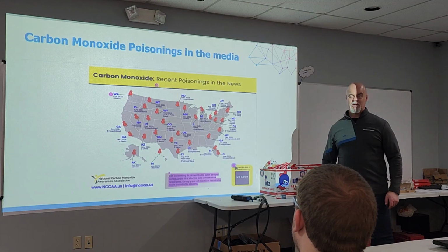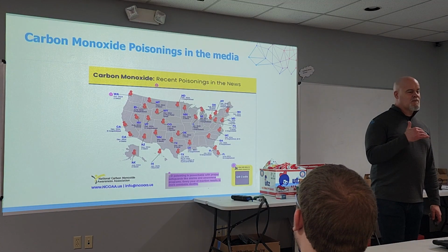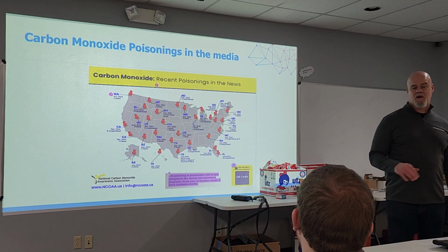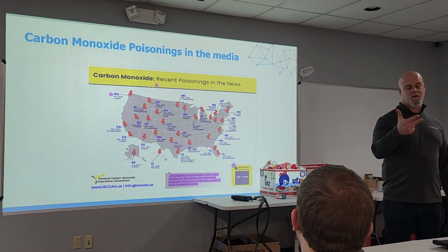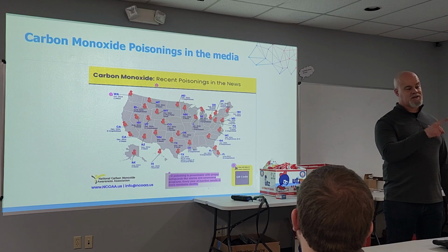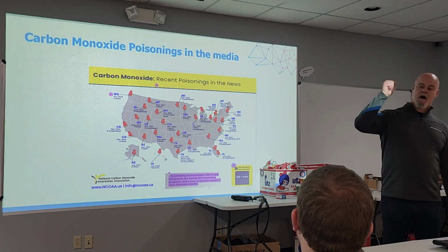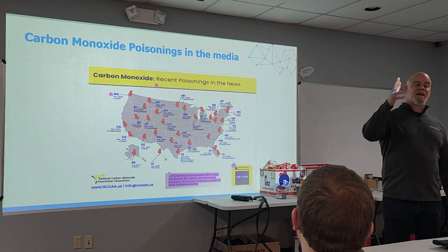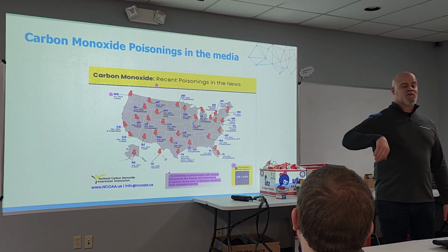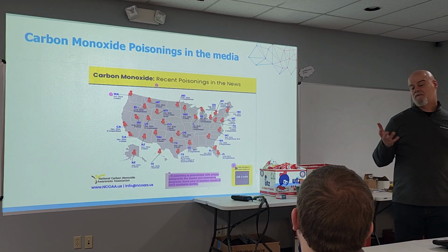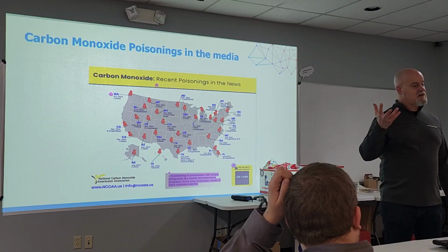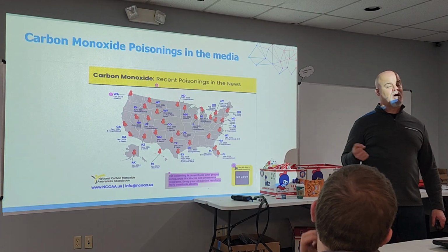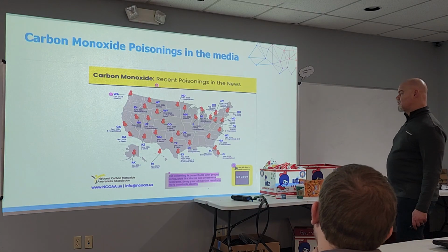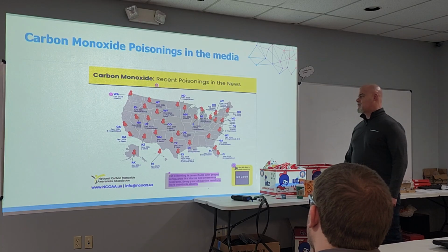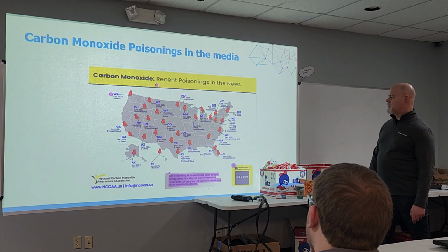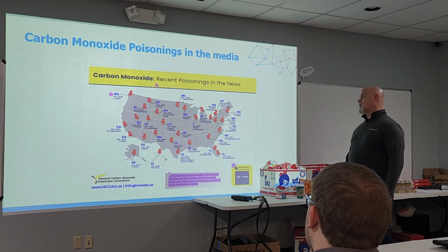Because when you do your ambient sweeps, you could be there solving a problem that you were never sent there to solve. They can have an issue with an oven, stove, water heater. By the way, the most common offenders of carbon monoxide poisonings are the following: ovens, stoves, water heaters, and then furnaces and boilers. So as you're the mechanic there working on the furnace or the boiler or even the water heater, you could find an issue with another part of the house just by doing your monitoring of that ambient environment. So very, very important. And these are just a list of the poisonings that had happened as of last year. I should get an updated chart on that, but it happens quite frequently all around the country, okay?